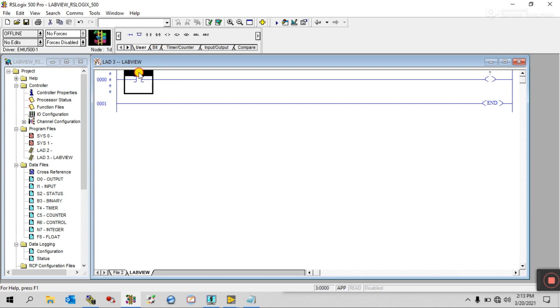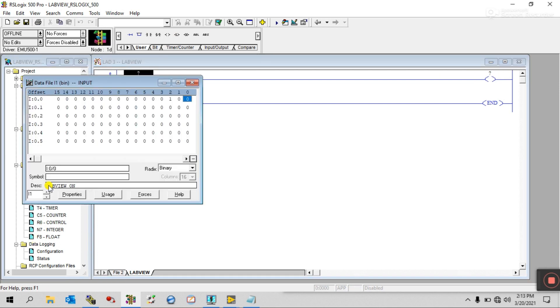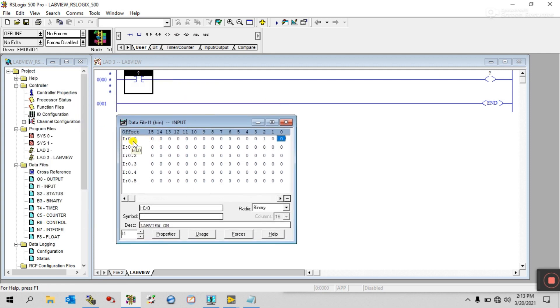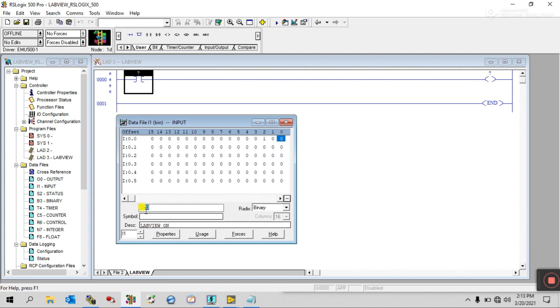Now you need to enter an address here. This is input, so open the data file. Use address like I:0/0 — this is I:0/0 and I:0/1. We need I:0/0. Copy this tag and paste it here.